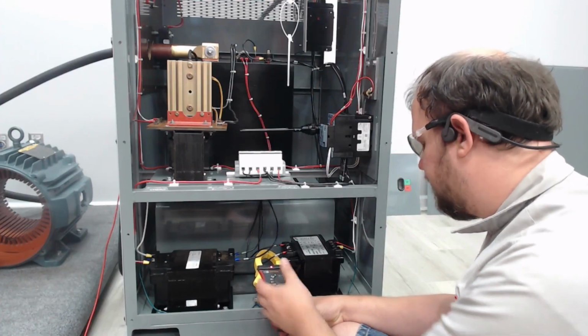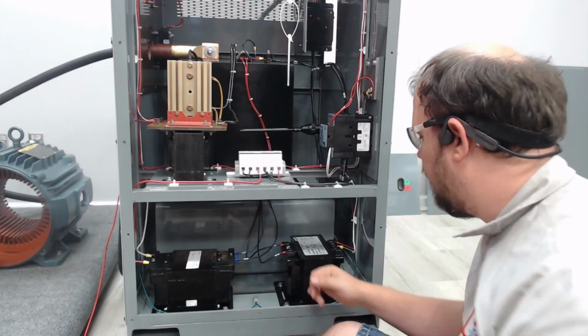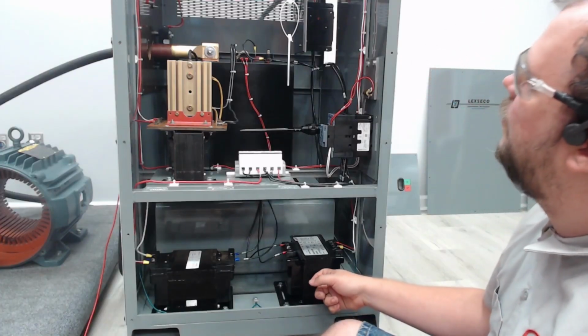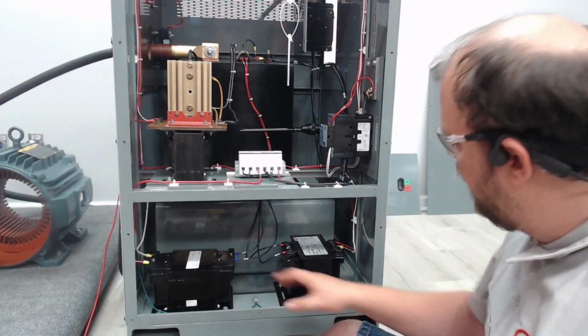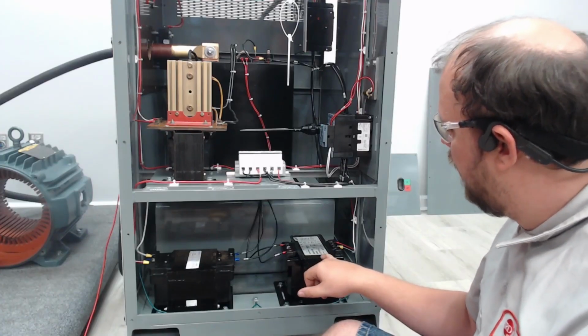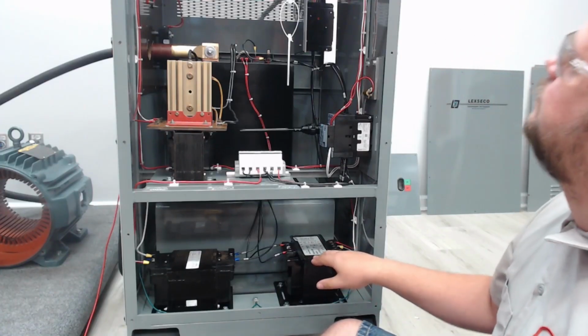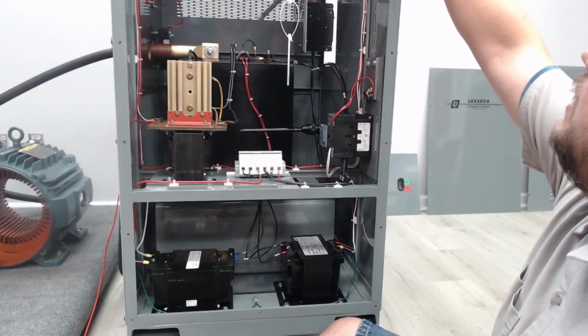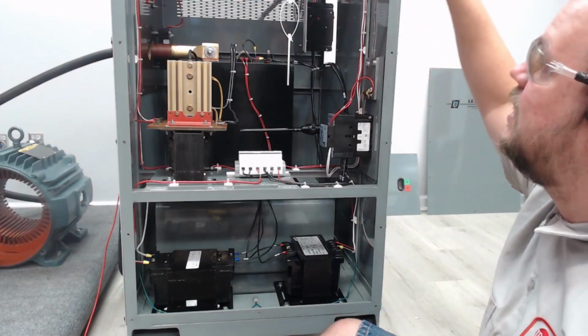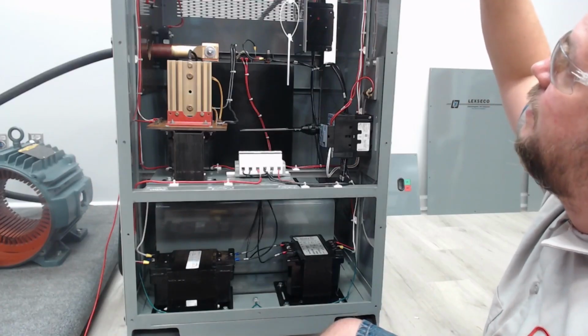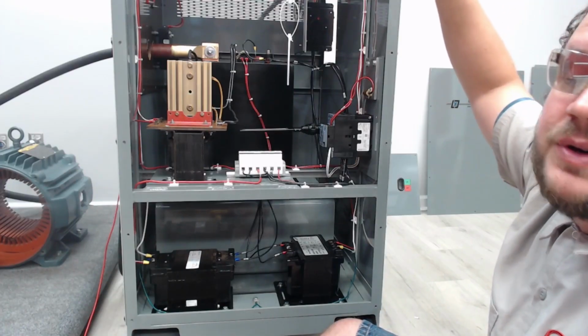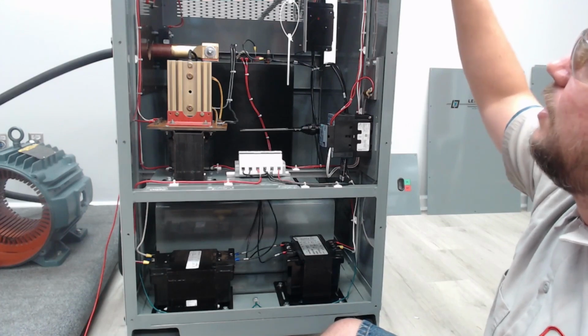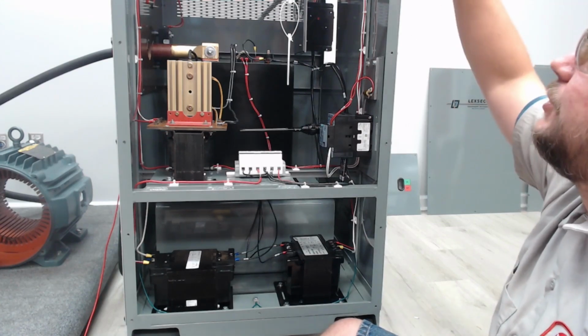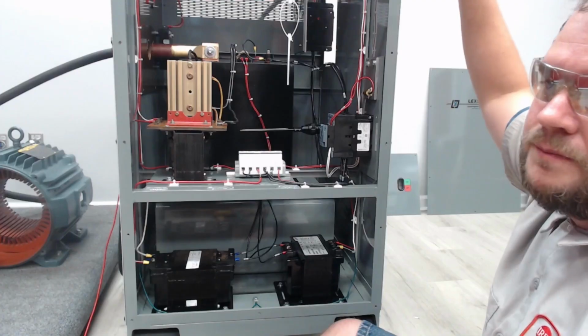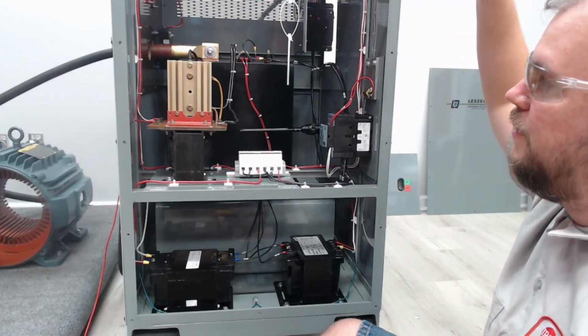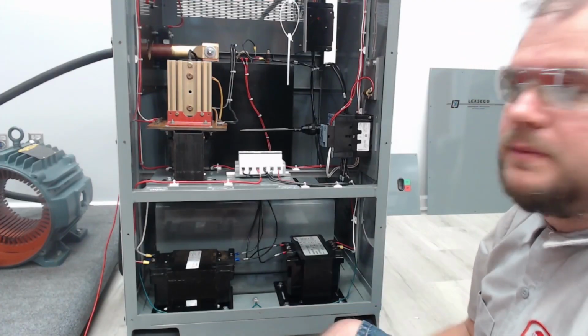So I have almost no draw on that small transformer. This 0.5 kVA transformer, it doesn't matter where it is. It's going to be the 500 VA transformer, just powering the meter and the laptops. That's all it's powering. So there's really never going to be any draw. If you do have any significant draw, then obviously something has gone wrong, and you need to go downstream and figure out what's increasing that current draw to be more than 0.1 nominal.